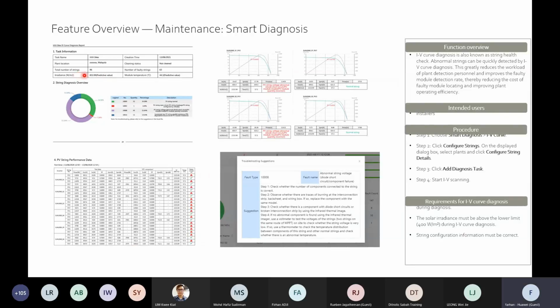Here we give you task information - how many strings you have, the number. There's a summary that tells you how many strings have issues. For example, if there's one issue detected on PV2, your guy only needs to go to the site and check that one PV string only, no need to check every string. They dismantle one PV string, which may have 20 pieces of PV module, and only need to check that one.